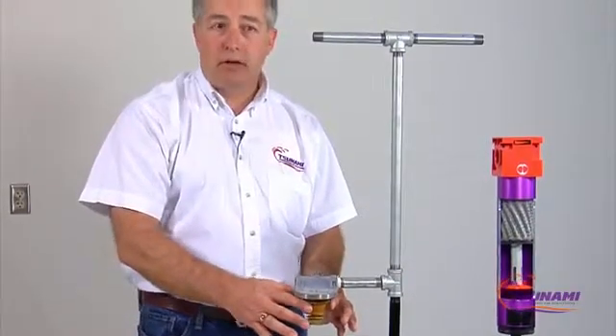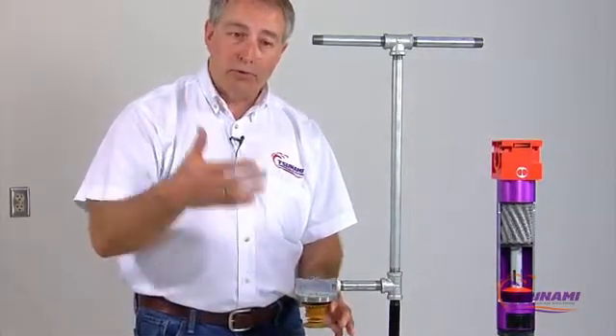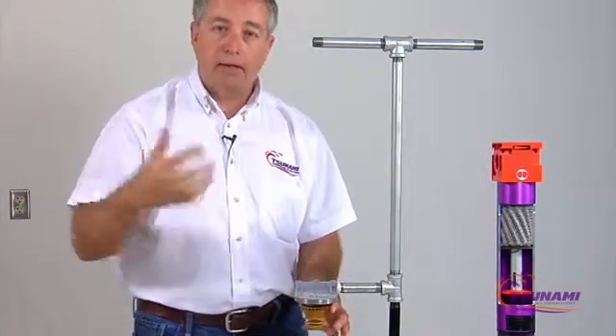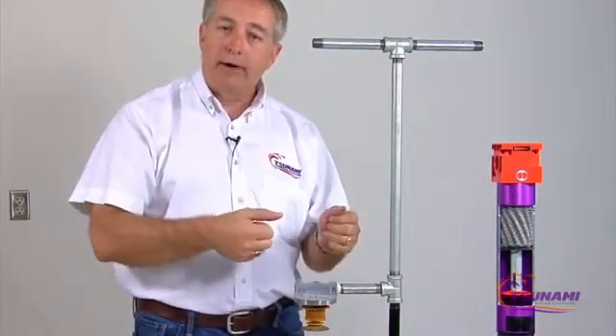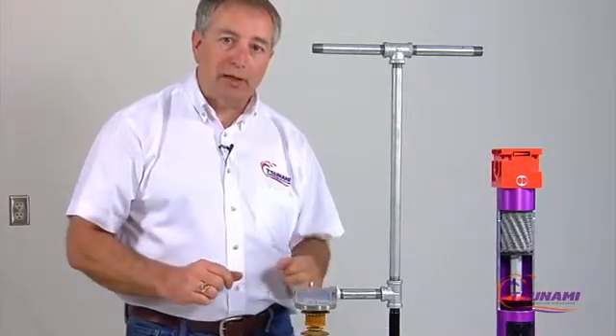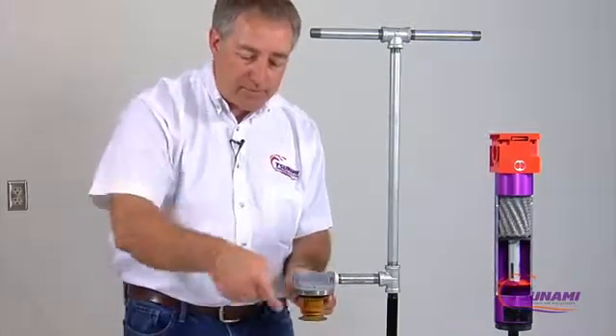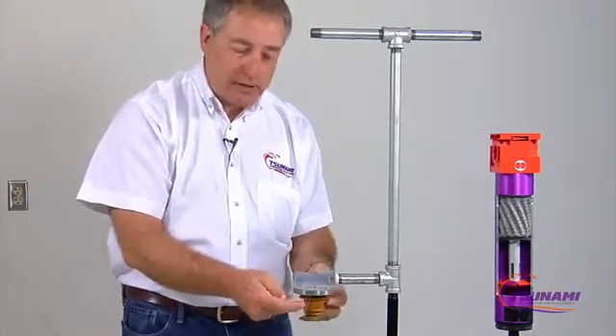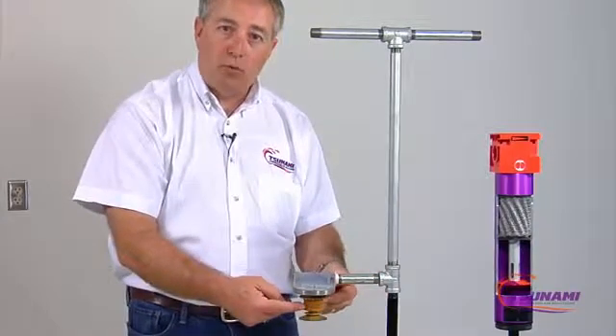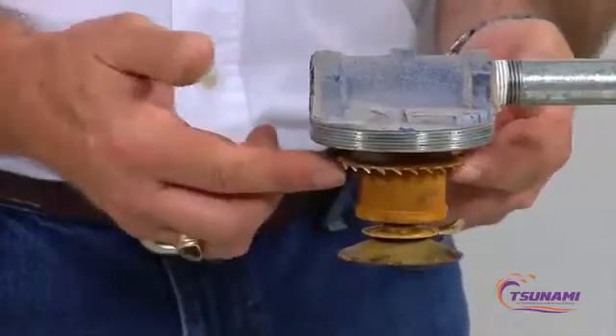But what happens all day long is you have periods of really low flow or no flow, and you have real high flow. A person's using an air tool, turns it on and off. Squeeze a trigger on a paint gun, you're using air, hit a tire changer, inflate a tire, so you get big bursts of air that happen in your shops and your plants all day long. And your elements are all right up at the top. Those droplets come in and they'll impinge themselves right against that element, and the liquid will be driven right through that porous element. So you get water and oil droplets that'll carry over downstream.